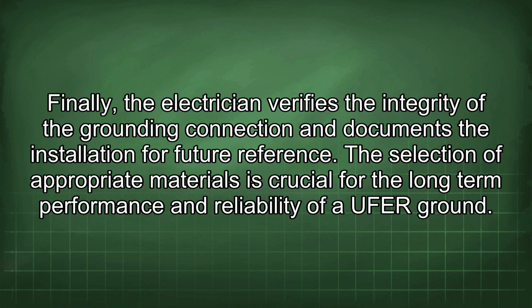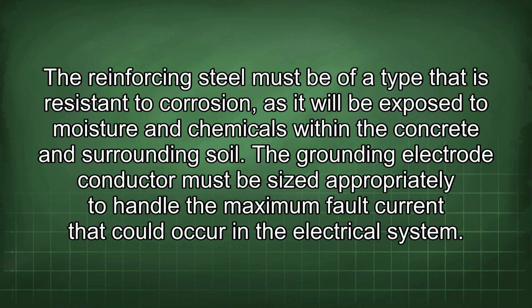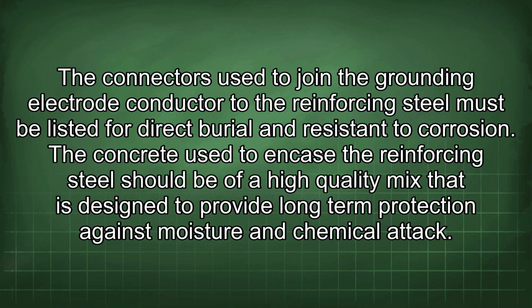The selection of appropriate materials is crucial for the long-term performance and reliability of a UFER ground. The reinforcing steel must be of a type that is resistant to corrosion, as it will be exposed to moisture and chemicals within the concrete and surrounding soil. The grounding electrode conductor must be sized appropriately to handle the maximum fault current that could occur in the electrical system. The connectors used to join the grounding electrode conductor to the reinforcing steel must be listed for direct burial and resistant to corrosion. The concrete used to encase the reinforcing steel should be of a high-quality mix that is designed to provide long-term protection against moisture and chemical attack.